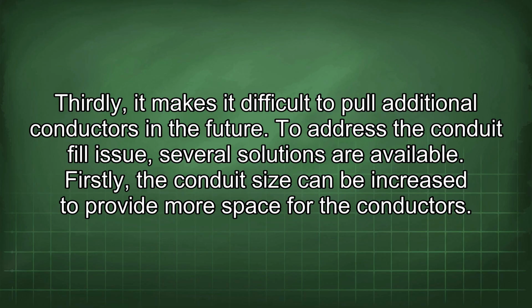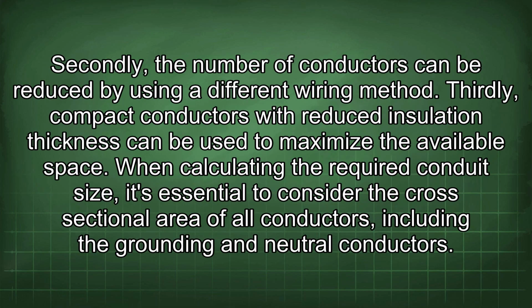To address the conduit fill issue, several solutions are available. Firstly, the conduit size can be increased to provide more space for the conductors. Secondly, the number of conductors can be reduced by using a different wiring method. Thirdly, compact conductors with reduced insulation thickness can be used to maximize the available space.